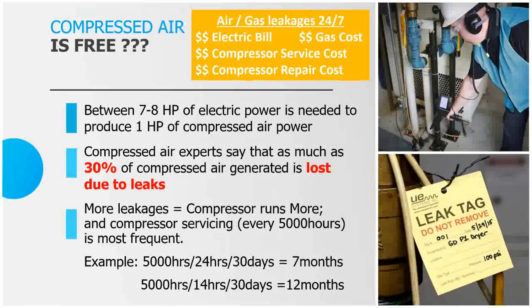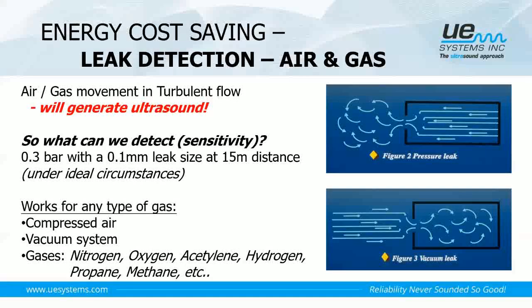So if we're having air or gas leaks 24/7, we are paying for the electric bill. If there is a gas leaking, we are paying for the gas cost. We're also paying for the compressor service cost as well as the compressor repair cost. So compressed air is actually not free. Air and gas movement in turbulent flow will generate ultrasound. It's regardless of leak out or leak in. As long as there is a pressure difference, turbulence is generated and ultrasound is detectable.